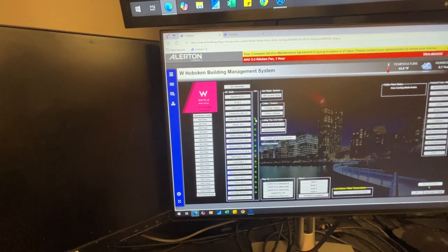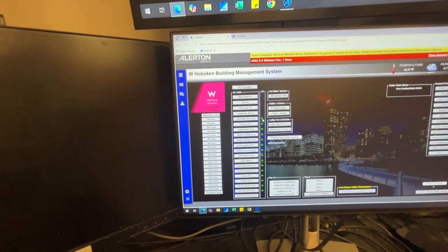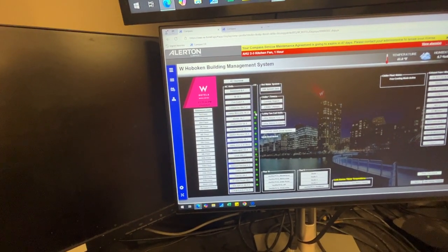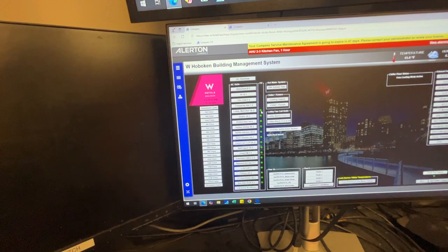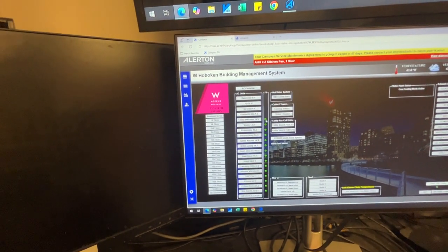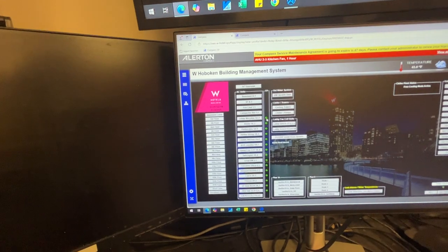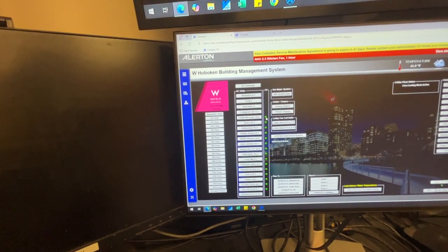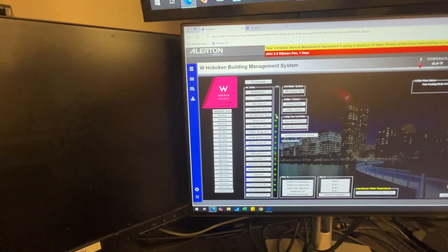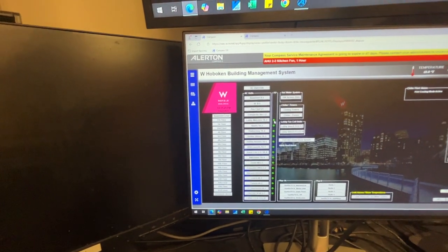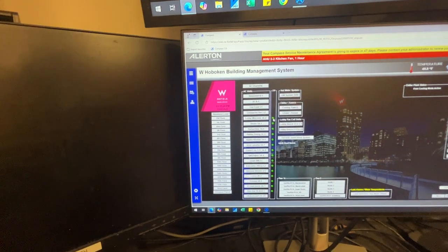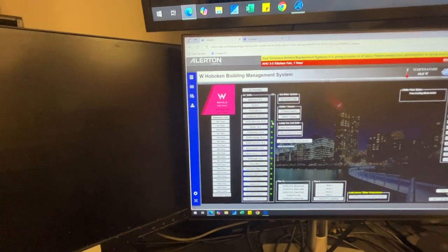The freeze stats are after both coils, which is very stupid. I mean, they were designed to be in between the hot water and the cold water coil, but they're after both. Do not change them to 32 degrees. Someone did that at one point. We broke like 4 coils before I got here. I got here and there was 4 broken coils we had to replace. So they are supposed to be set at 41 degrees. That's what it shows in the prints as the design. So don't set them any lower.